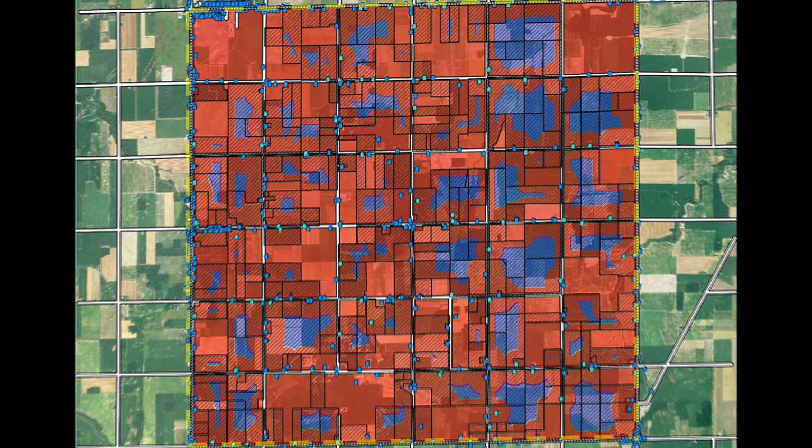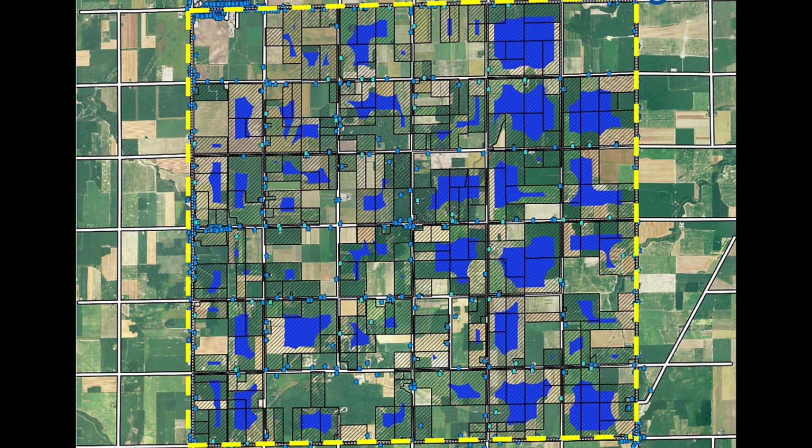What that leads us to then is we've put a whole bunch of setbacks on here. We might also, on top of what I'm showing in this slide, apply additional environmental, wildlife, wetland setbacks. They're not included in this map. This site has very few of those areas. But that is part of our process as well. And we come to anywhere from as low as maybe 15% of the total area might be left up to maybe 30-35% from what we started with, depending on just how heavily populated it is and how many constraints and what setbacks we're using.